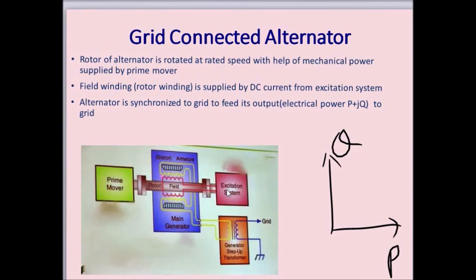Therefore, the alternator continuously feeds active power and reactive power into the grid. The reactive power fed into the grid depends on how much the generator is excited, and the active power fed into the grid depends on how much mechanical power is provided to the rotor of the alternator.